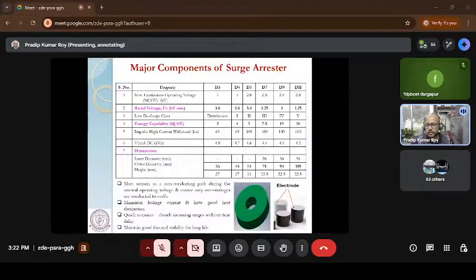So what is the major function of the surge arrestor? Initially it acts as a normal insulator. As soon as the surge comes, it will immediately act as a conductor. Again, when the surge goes back, it will act as an insulator. So this part you have to remember: initially insulator, then conductor, then again insulator. So how is this possible? This is done by some material characteristics that I'll explain later.